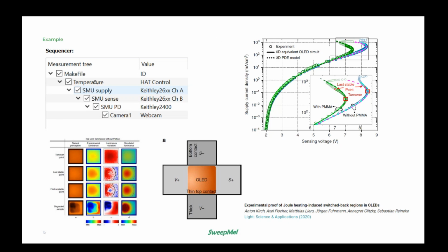So this time, the temperature module is not configured to make a temperature variation, but it is configured to keep the temperature constant and conduct all heat away to make sure we have good control over the environment. So it's again a measurement that you can configure in 5 minutes, using the same contents again without programming, just configuring these modules in a different variation.